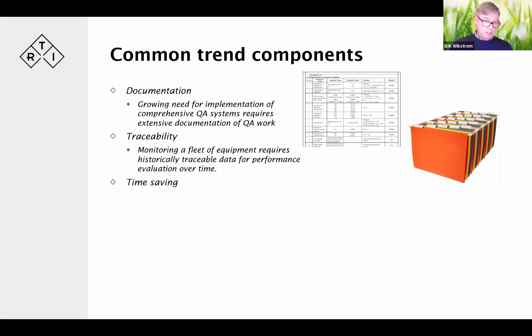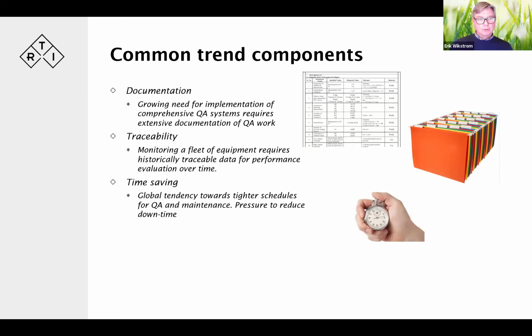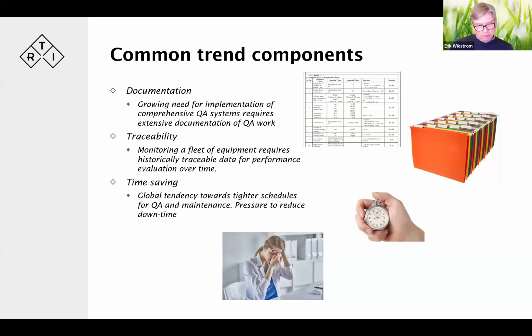Time saving, of course, is always there. You see a global tendency towards tighter schedules for QA and maintenance. Maybe not so much on general radiography, but definitely on CTs and mammo and dental machines. There's less and less time allotted for QA, maintenance and testing. So there needs to be some form of time saving in there. And of course, that puts pressure on us in the market. How do we actually cope with this? Because we need to do more in less time. So how does that compute?